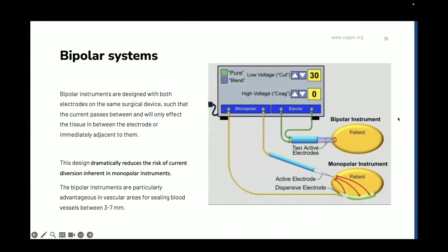So this is kind of the meat of what I've been talking about. So tissue effects, and how can you as a surgeon, what can you alter to achieve different tissue effects for your patient based on what you're trying to get? And the way I see it, you have basically 4 things that you can alter, manipulate to get the desired tissue effect. The first one is your power setting, the setting that you're setting on the machine, the waveform, which is either coag, cut, or a blend. The speed at which you're moving your instrument through tissue, and tissue contact, which can affect your current density, how much of your instrument is touching tissue, or whether it's touching at all, because you can also arc your current 1 millimeter away from the patient's tissue to achieve certain tissue effects.